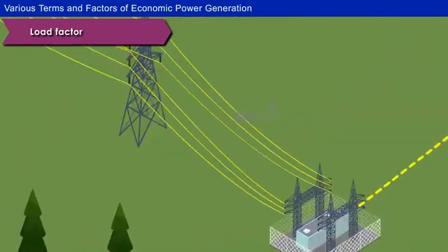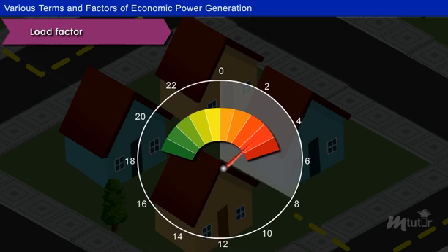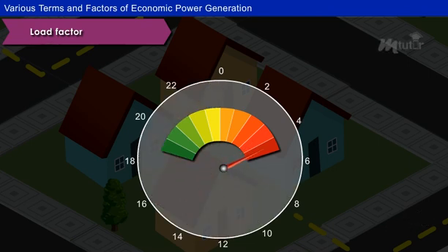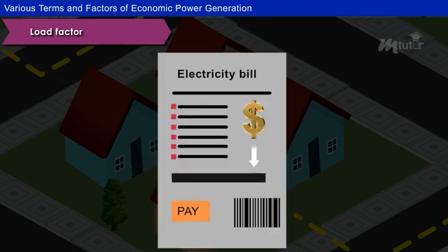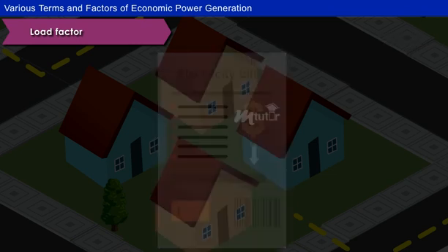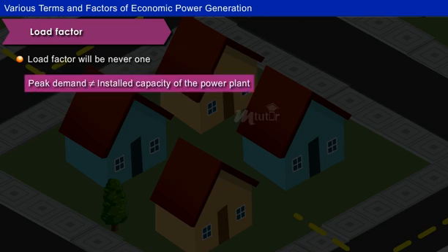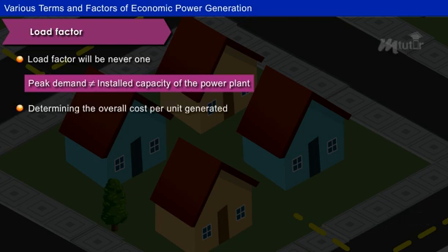Whenever a power plant is constructed, it is designed to serve the maximum demand of the consumers. If the consumers maintain the maximum demand throughout the day, then the fullest capability of the power plant will be utilized and it will reduce the cost of the electricity bill. But practically, this is not the case. The load factor will never be one, as the peak demand is not equal to the installed capacity of the power plant in the actual case. Thus, the load factor plays a key role in determining the overall cost per unit generated.